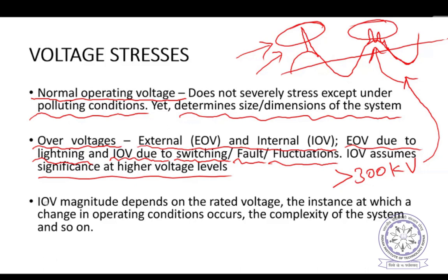Now, internal over voltage, that is switching voltage, magnitude depends on the rated voltage of the power system, and the instance at which a change in operating condition occurs, whether you have switched it on at zero crossing or at 90 degrees phase angle. All this will decide the over voltage magnitude. And the complexity of the system, how complex the system is, also affects the over voltages.